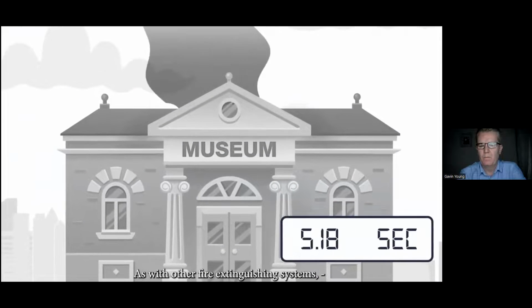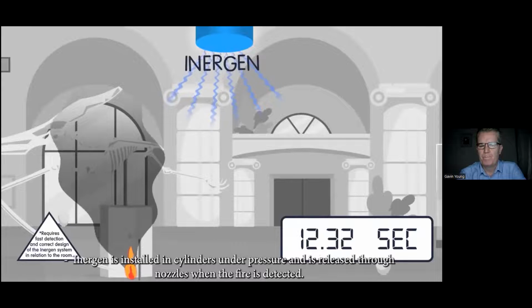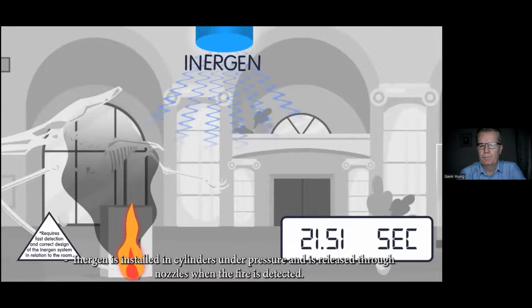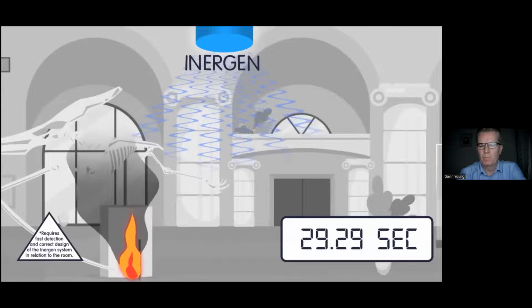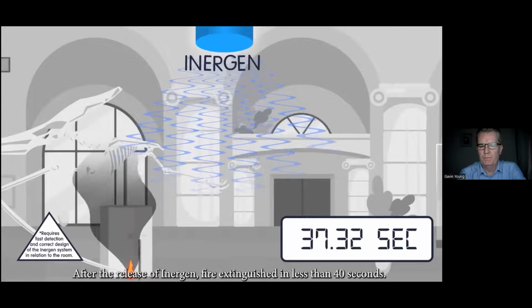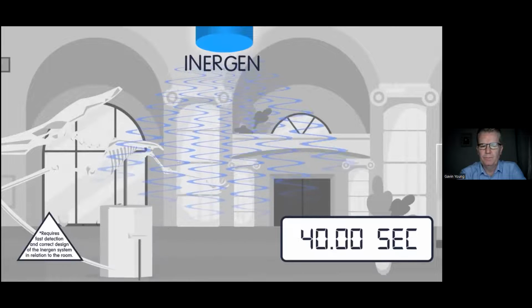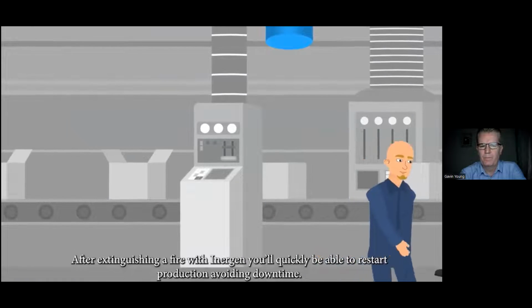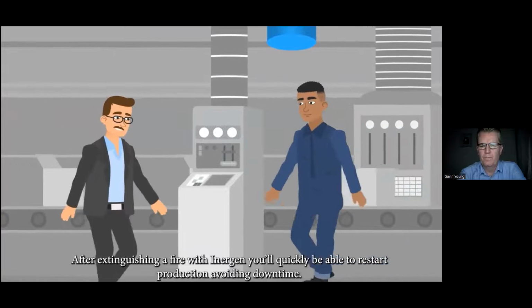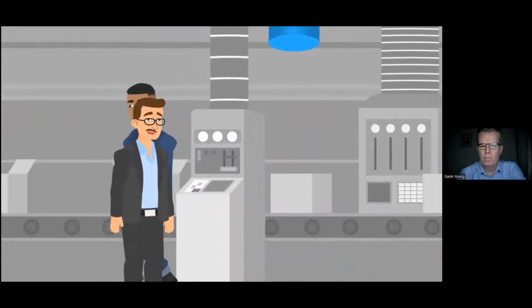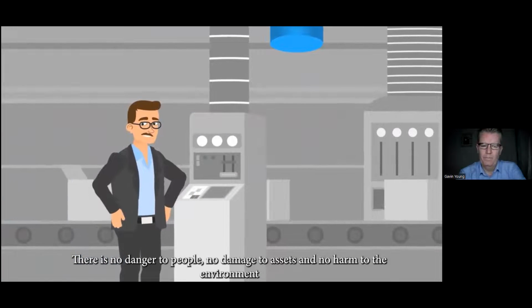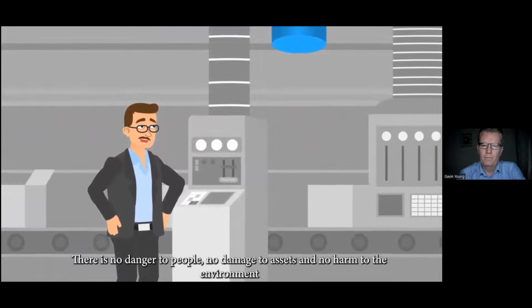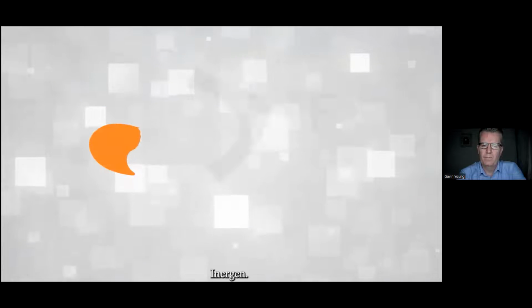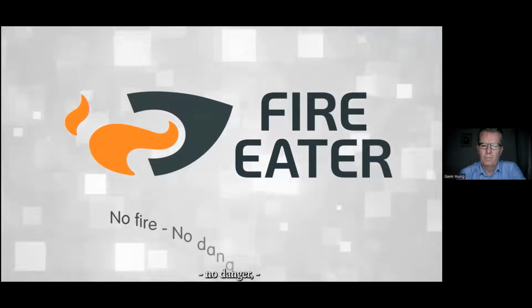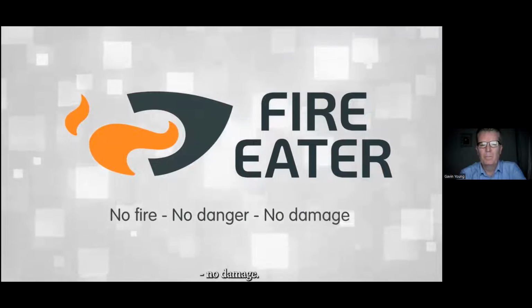This way, the fire is extinguished and prevented from spreading. As with other fire extinguishing systems, Inergen is installed in cylinders under pressure and is released through nozzles when the fire is detected. After the release of Inergen, the fire is extinguished in less than 40 seconds. After extinguishing a fire with Inergen, you'll quickly be able to restart production, avoiding downtime. There is no danger to people, no damage to assets, and no harm to the environment. Inergen. No fire, no danger, no damage.